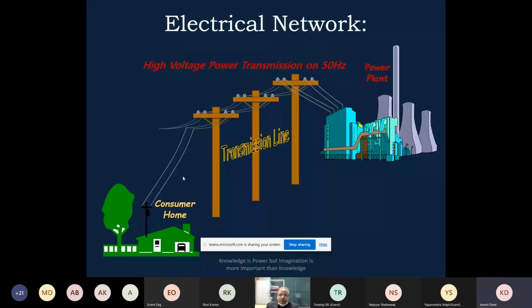For example, instead of 6.6 kV or 11 kV, if we consider 66 kV, it requires very huge and bulky insulation, so the cost of the machines will be very high. If we consider a very low voltage like 3.3 kV for an 80 megawatt or 100 megawatt machine, then the conductor size will be very large, and again the cost will be very high and I squared R losses become very high. So optimal utilization of generation depends on the machine size in MVA, the voltage level, and then the conductor size.